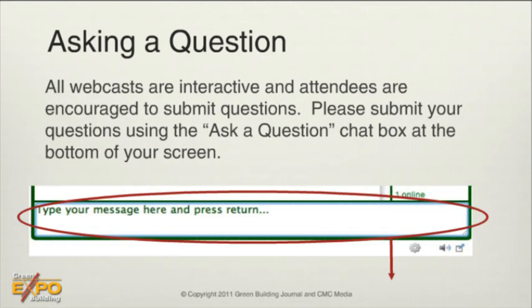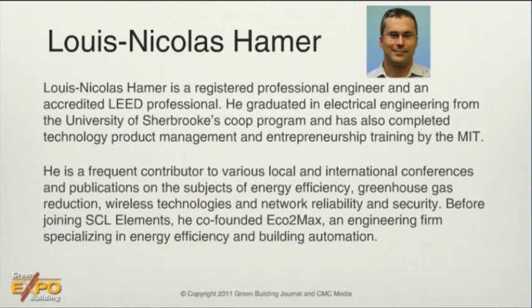It also really varies depending on the use of that building. Is it a hotel? Is it a building office? So it's kind of hard to answer that question, and it will vary greatly. The way the industry really works is they don't price it per square foot, they price it per control point, and that's a better way of coming up with a rule of thumb for how much a system will cost.